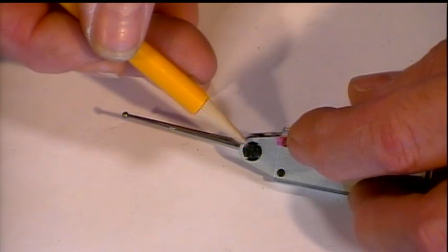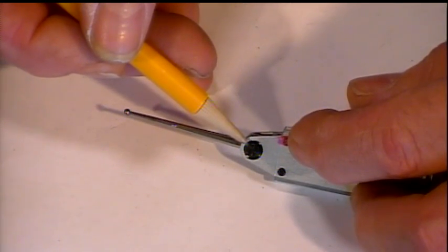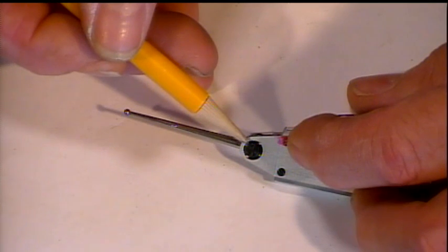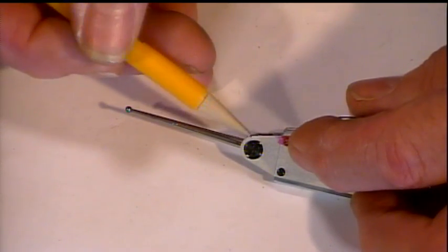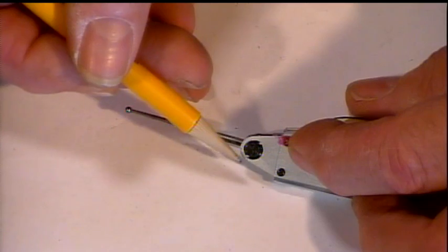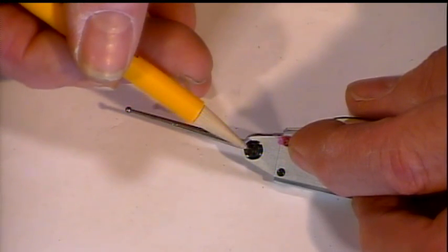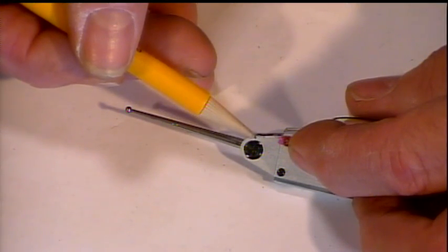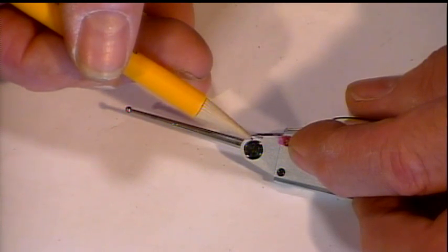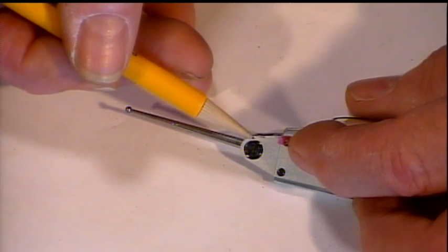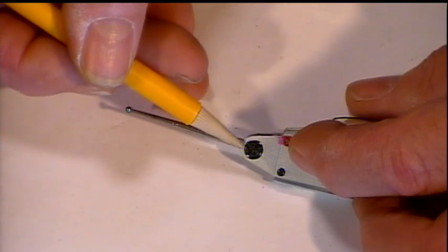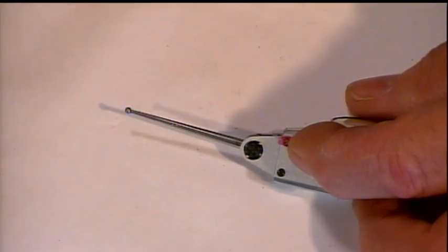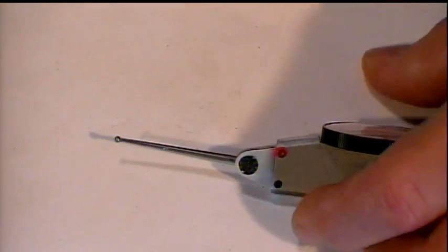We don't really advocate adjusting them, but sometimes you may have to. The contact point is almost falling out and you can see the screw is backed way off. This has a locking ring - normally we'd loosen that, bring the screw down until it just touches or almost touches, then slightly lock the locking ring. You want to avoid doing that though - that's best left to people with the proper training. Having the right tools is one thing, but understanding the proper training is something else.